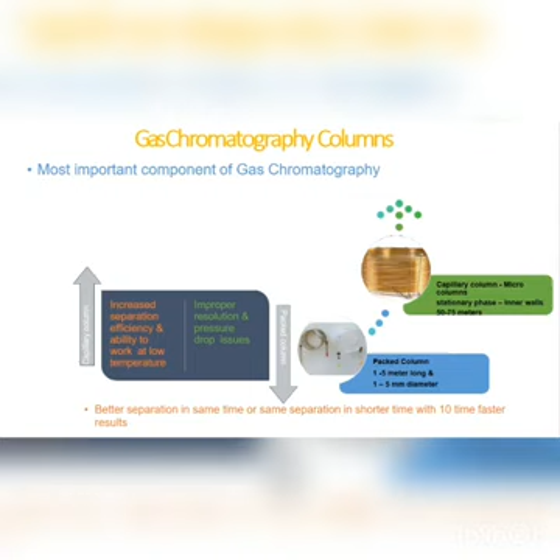Now, the next part is the column, the most important component of gas chromatography. Here, 2 types of columns are used in GC, the capillary column and the packed column. The capillary columns are micro in size and have the stationary phase on their inner walls, and the length of a capillary column is 50 to 75 meters. Due to this long run of the column, the separation becomes efficient, while the packed column is 1 to 5 meters long and 1 to 5 millimeter in diameter. Capillary columns have increased separation efficiency and the ability to work at low temperature, while packed columns have improper resolution and pressure drop issues. Capillary columns give better separation in the same time, or the same separation in shorter time, with 10 times faster results.